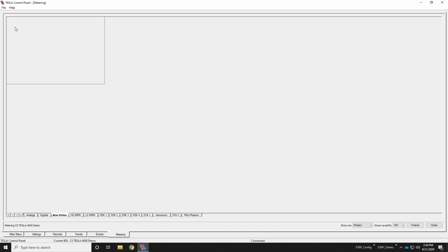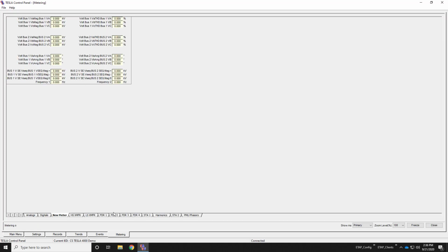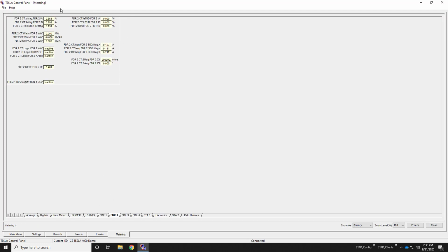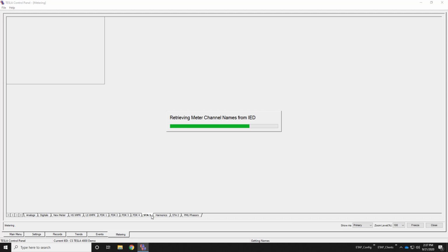Next is the metering. In the metering section, we can see real-time data in the field. So here's the actual measured data on the device. So this is feeder 2, showing the actual current magnitudes, the calculated watts, etc. Additionally, we have our statuses from the device.